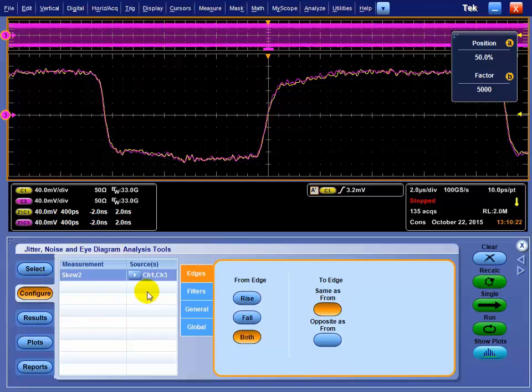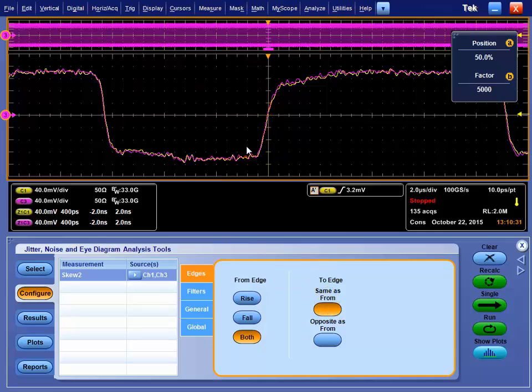In the configuration, there's a couple things you can check. If you did use a splitter so you have the same phase of signal, then you want to check it relative to the same edge. You could also do this just hooked up live to the device.